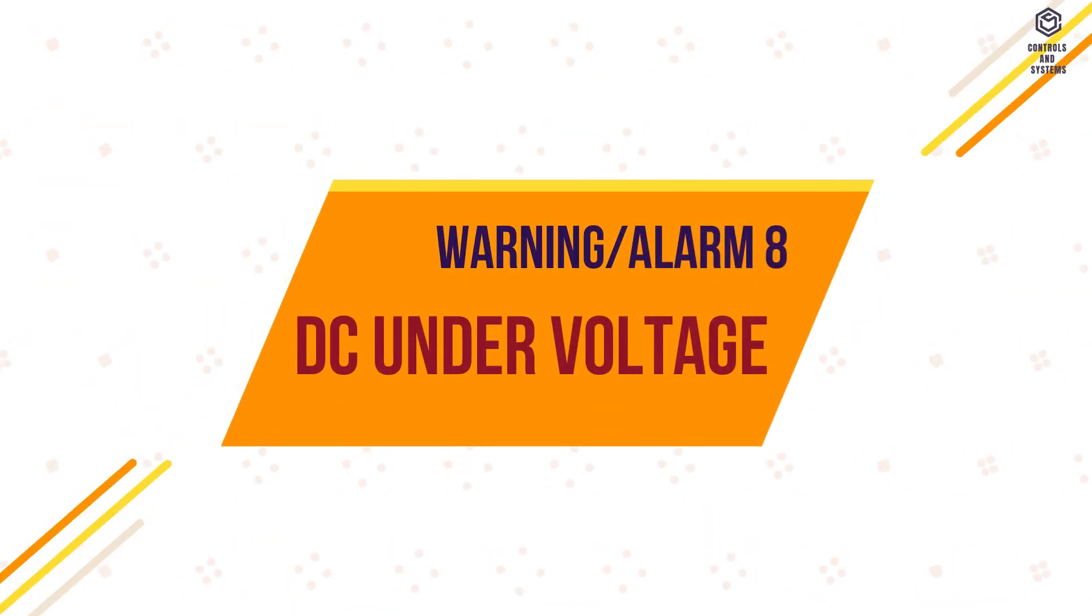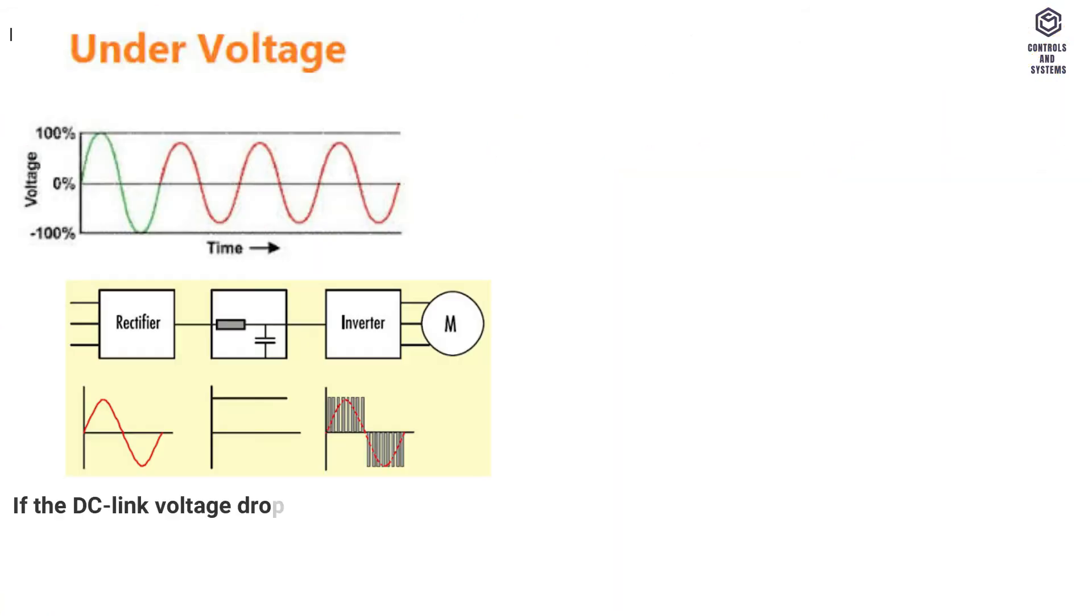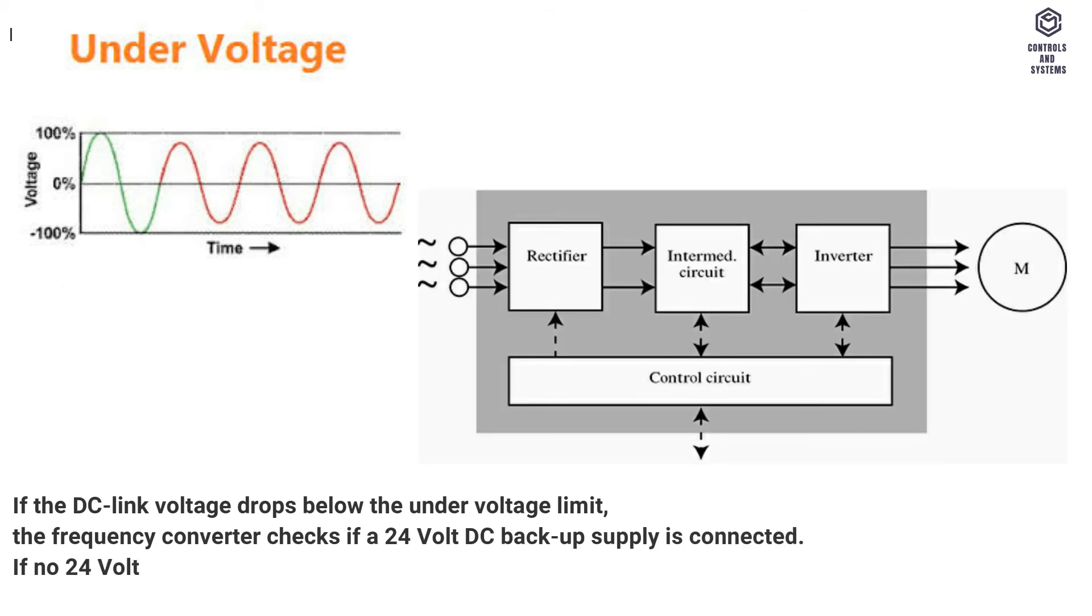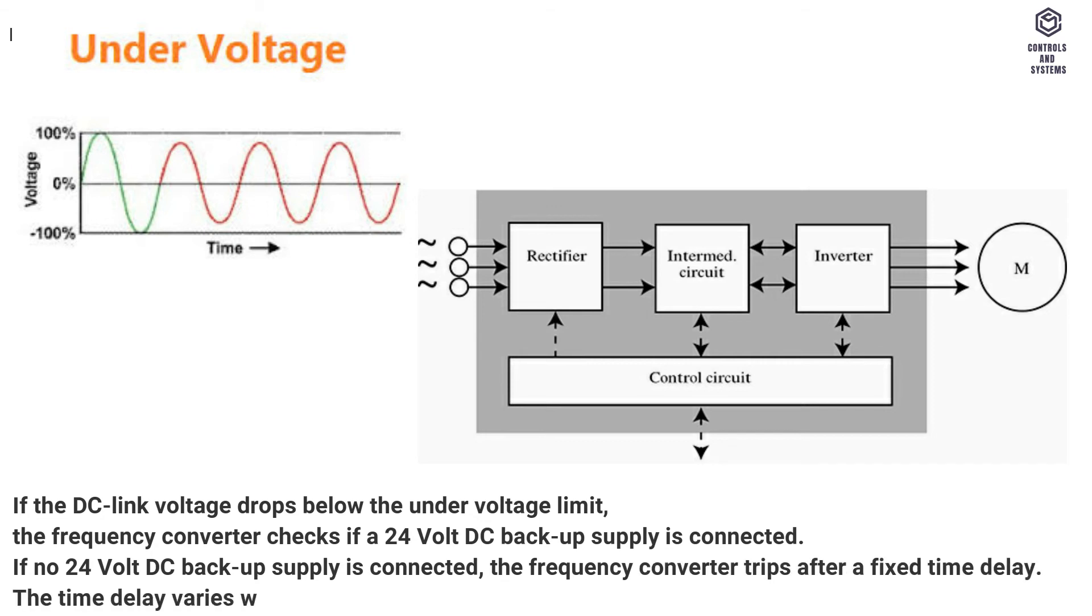Warning, Alarm 8, DC Under Voltage. If the DC link voltage drops below the under voltage limit, the frequency converter checks if a 24 volt DC backup supply is connected. If no 24 volt DC backup supply is connected, the frequency converter trips after a fixed time delay. The time delay varies with unit size.